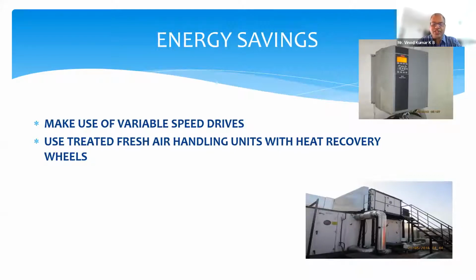So you need to change your starters from normal DOL or star delta starters to variable frequency drives, wherein you can set the speed of the AHUs for the daytime at a particular speed where the cooling is required for these surgeries to happen. At night, when the surgeries are not happening, you can reset the temperatures as well as reset the speed of the VFD to a lower speed, so that the pressure and the temperature in the theater are still maintained at around 21 plus or minus 1, and you have a good level of contamination control.